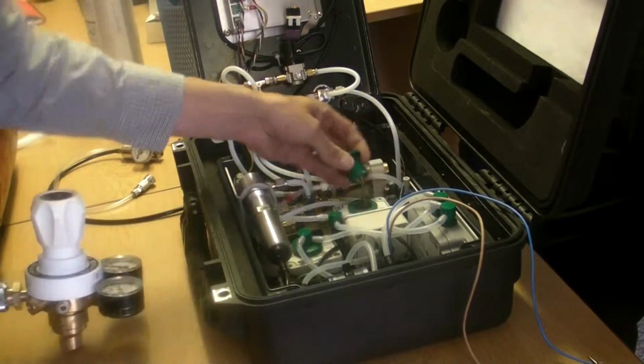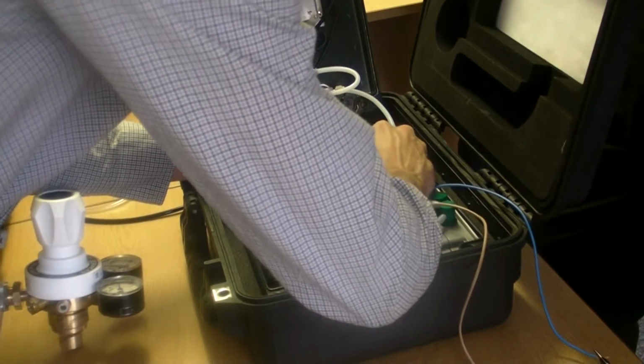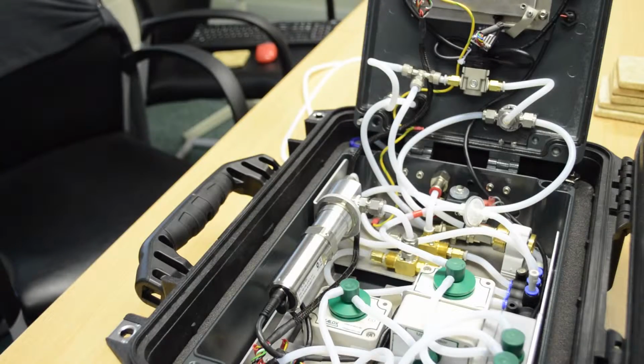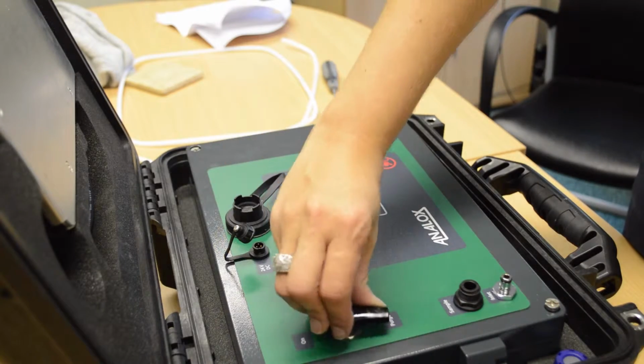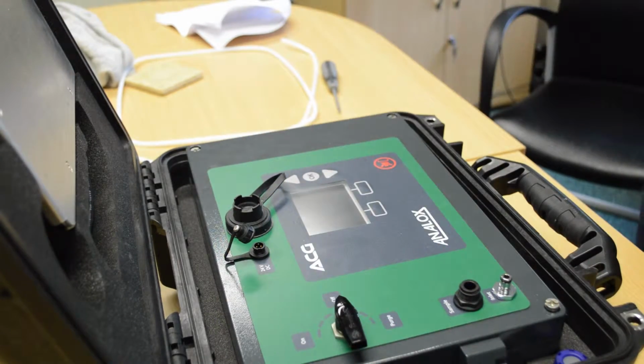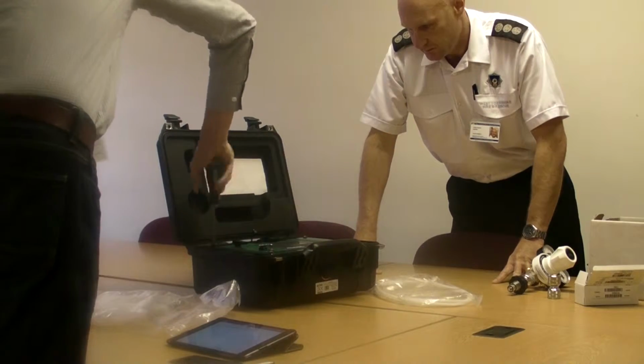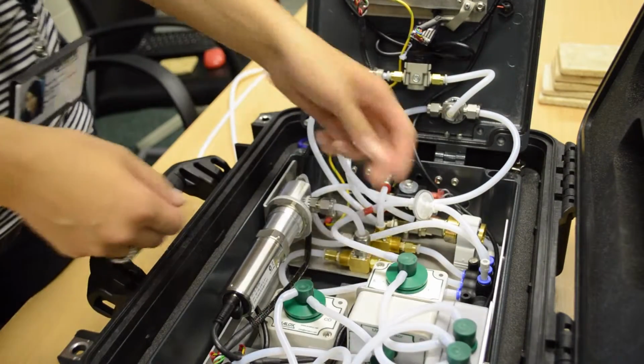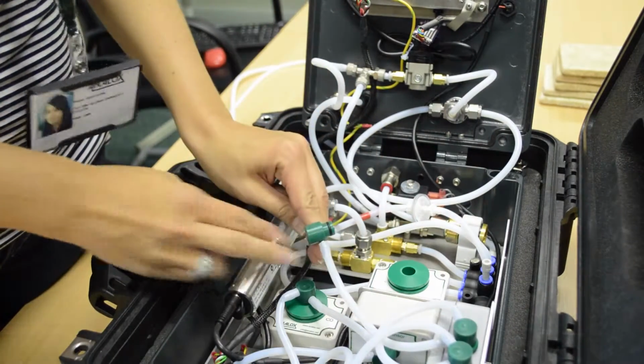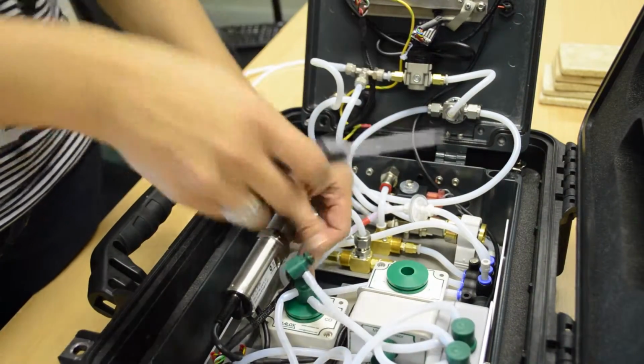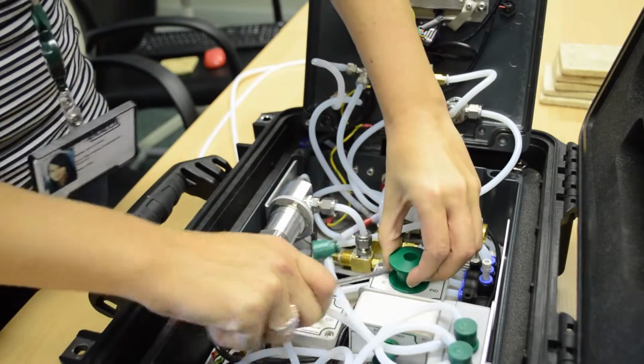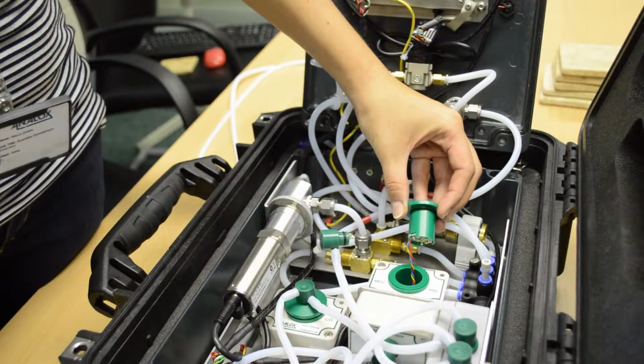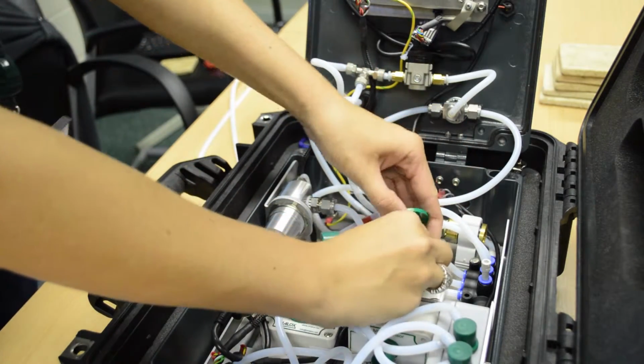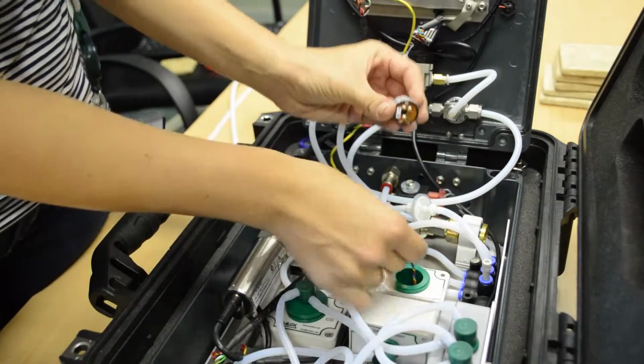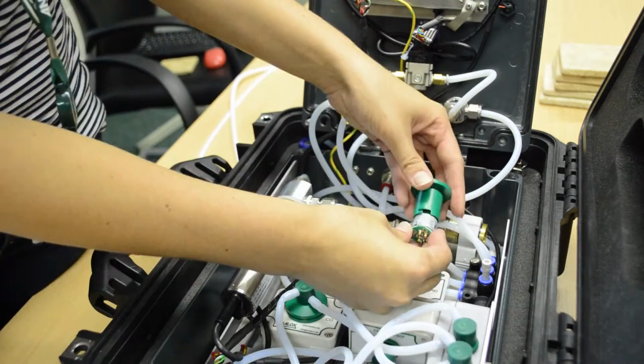Certain elements of the ACG Plus system require regular, preventive maintenance to ensure optimum operation. Before attempting to replace any filters or sensors, ensure that the ACG Plus is switched off and the gas supply has been isolated and disconnected. Using a posi drive screwdriver, loosen the 4 enclosure lid screws and open the lid. Remove the flow adapter from the sensor inlet. Loosen the corner screws of the enclosure and remove the lid. Using a terminal screwdriver, push down the clamp release button to release the clamp and gently pull the cell wire from the clamp. Repeat this for both the red and black wires. Unscrew the green locking ring from the chimney of the cell housing and remove the enclosure lid. Fit the new cell into the enclosure lid and secure it in place with the locking ring.